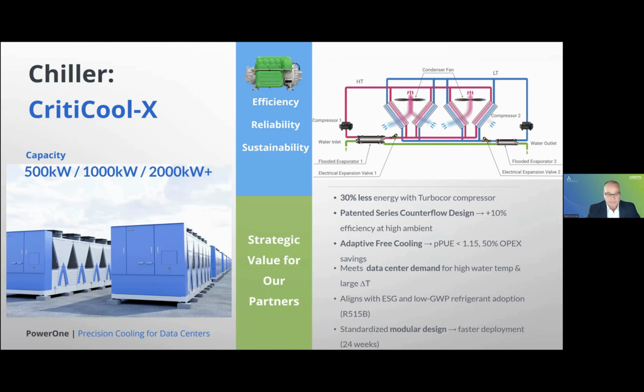Our CritiCool product. This is basically our chiller set. We have the capacity of 500 kW, 1 megawatt, 2 megawatt. We're building this as well as we're seeing 2.5 megawatts, so we can do more in a smaller footprint. We have utilized the Turbocor oil-free mag bearing compressors, our patented series counterflow product, adaptive cooling. We are also providing this with low global warming potential R515B refrigerant. And we have a standard modular design based off that 53-foot length I mentioned earlier, and fast deployment. We're looking at the ability to get chillers into the marketplace within 24 to 30 weeks.